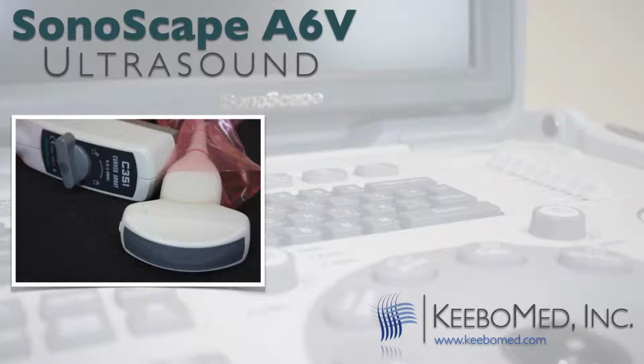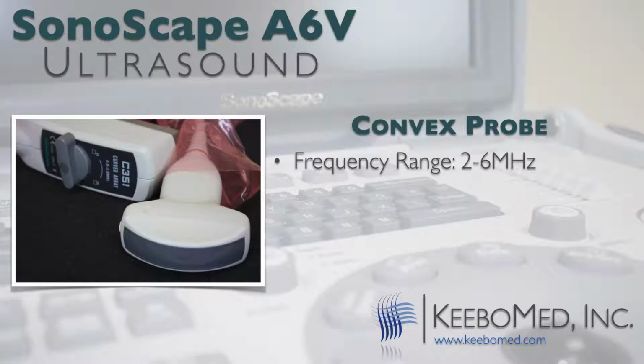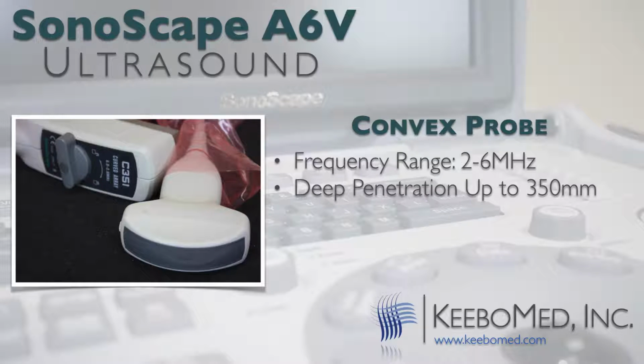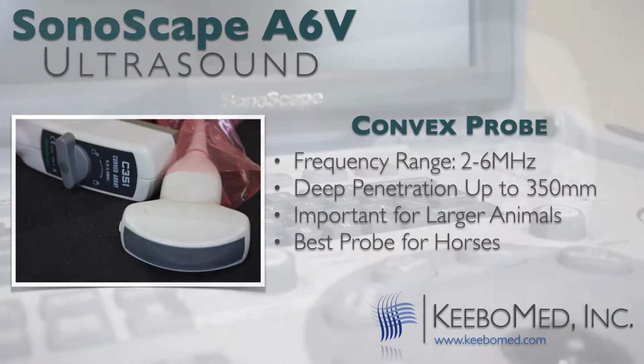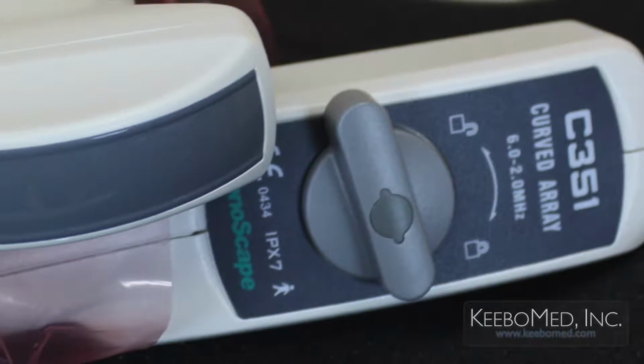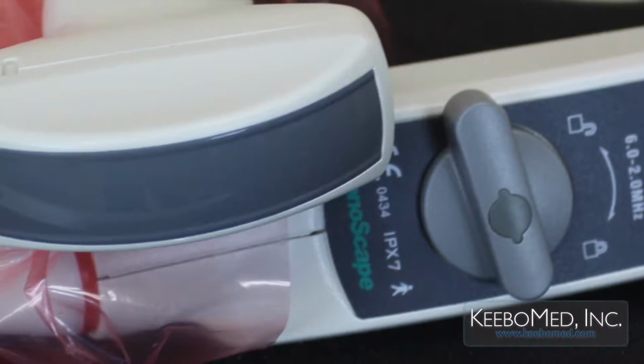The convex probe is also very unique. This probe has a frequency range of 2 to 6 MHz. It also penetrates very deep, up to 350 millimeters. Other ultrasounds have convex probes that only penetrate up to 250 millimeters. Depth is very important for checking bigger animals, such as larger goats, sheep, pigs, and even horses. There is not another convex probe on the market today that works better for horses than the convex probe found on the A6V.